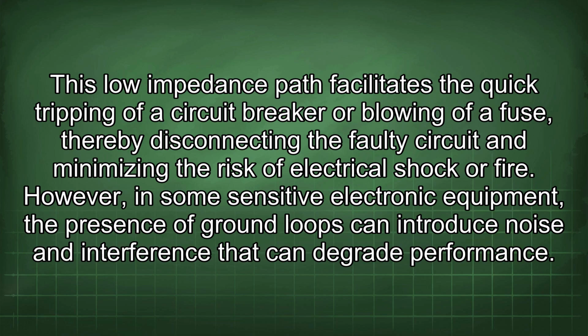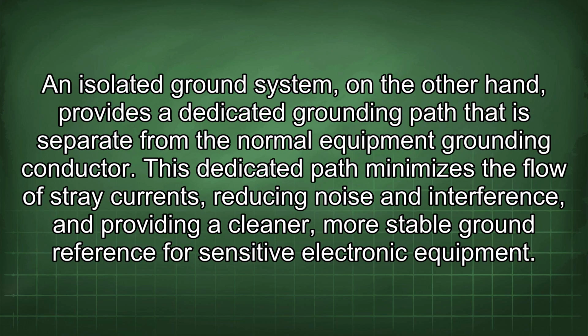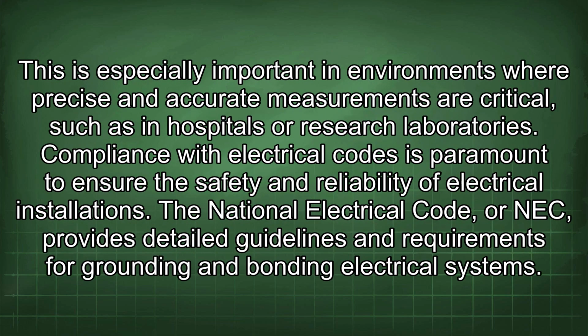However, in some sensitive electronic equipment, the presence of ground loops can introduce noise and interference that can degrade performance. An isolated ground system, on the other hand, provides a dedicated grounding path that is separate from the normal equipment grounding conductor. This dedicated path minimizes the flow of stray currents, reducing noise and interference, and providing a cleaner, more stable ground reference for sensitive electronic equipment. This is especially important in environments where precise and accurate measurements are critical, such as in hospitals or research laboratories.